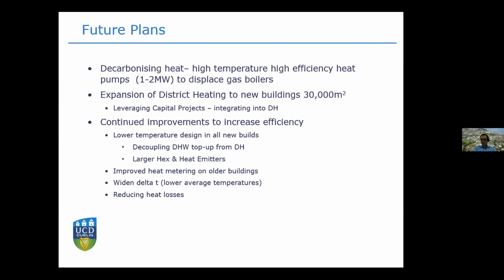We're looking at decoupling domestic hot water with local top-up—taking as much as you can from the district heating while operating it at a lower temperature, doing a smart top-up with potentially another heat pump or other methods. Larger heat exchangers and heat emitters, improving heat metering on some of our older systems is an area we want to look at, and widening the overall delta T. Lower average temperatures in the system means lower district heating losses, which is good, as well as the pumping benefits.